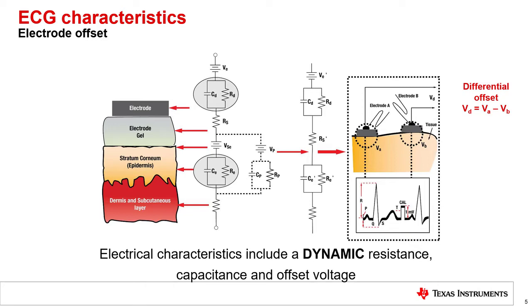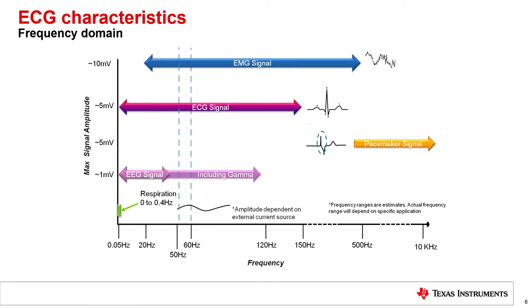The AC component of the ECG waveform is relatively low in frequency, usually between 0.05 and 40 hertz. Diagnostic quality ECG applications may require up to 150 hertz or more to extract additional information from the waveform. This diagram shows where ECG falls in the frequency spectrum relative to other biopotential measurements. Note the magnitude of the ECG is just a few millivolts. Later on in this presentation, we will also discuss the detection and measurement of pacemaker signals.